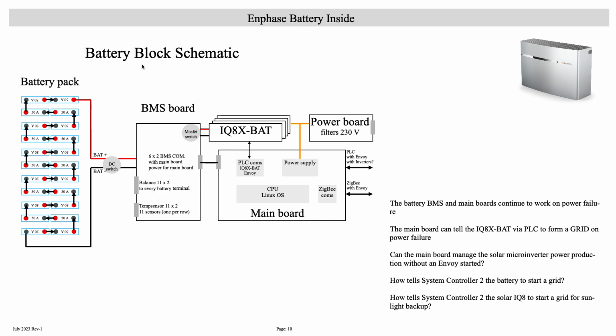So I was drawing a little schematic of how the whole thing works. Basically we have these battery cells in series. Then we have the battery positive and negative, a DC switch which connects the whole electronics and the battery, and this is very, very important: when the battery is not in use, turn off the DC switch. If there are problems, turn off the DC switch to make sure the batteries are not continuously being discharged by the boards or the inverters. When the battery is discharged and the voltage goes below 2.5 volts, this can hurt the batteries. It must not, but for a long period — weeks and months — kept below 2.5 volts, I'm sure the battery dies, or the individual cell dies.